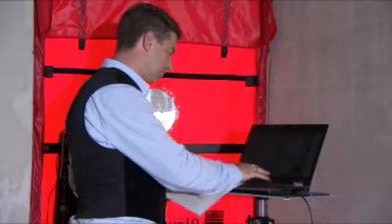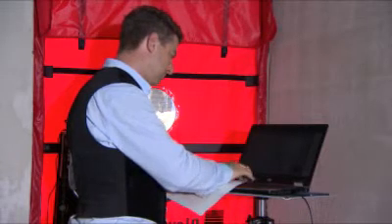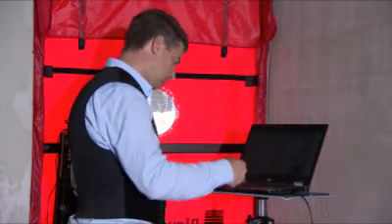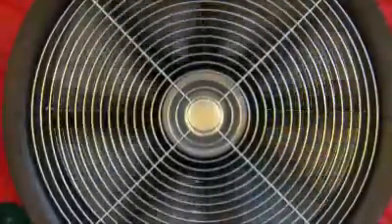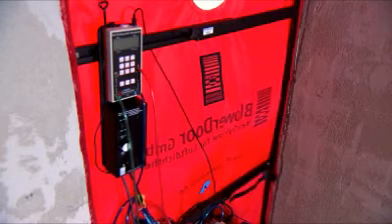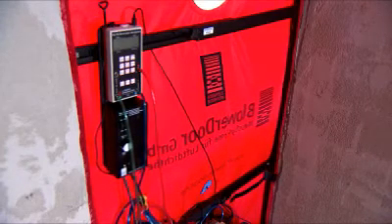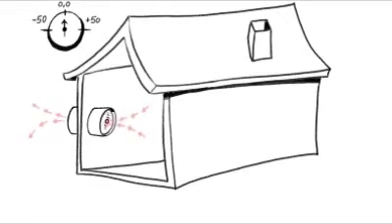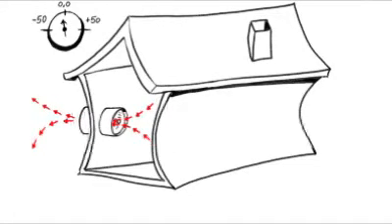The values required for measuring are programmed in and measuring begins. Negative pressure builds up inside the structure. The membrane at the measuring apparatus bulges inwards. The fan blows the indoor air out of the structure to produce a negative pressure of 50 pascal in the interior.